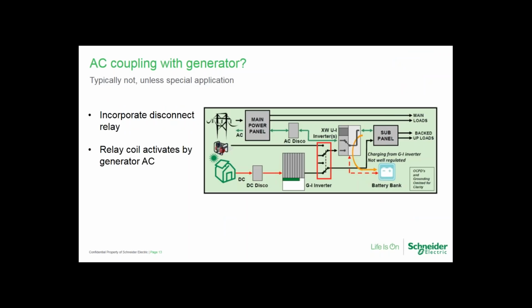So AC coupling with a generator, that's an important point because typically you're not going to want to export power back to the generator. Generators are not going to appreciate having their armatures spun backwards. So under no load conditions or low load conditions or negative current conditions, it's going to be important to incorporate an external means of disconnect so that anytime the generator starts, the AC power is removed from the grid tie inverter. So you can use a simple relay with an AC coil, 120 volt AC coil, and use line to neutral of the XWs on the generator input.